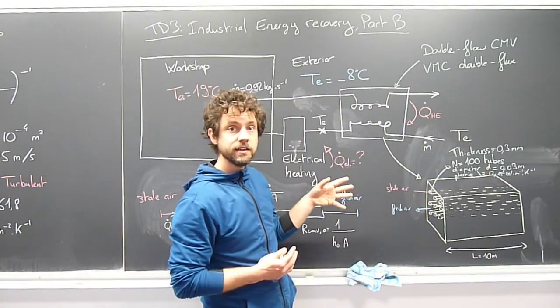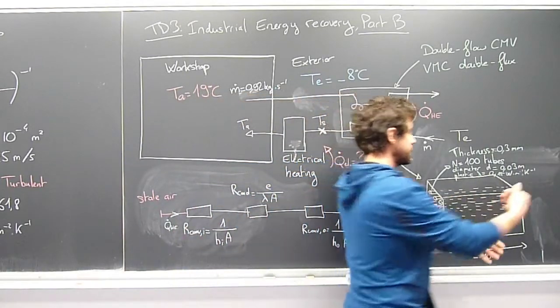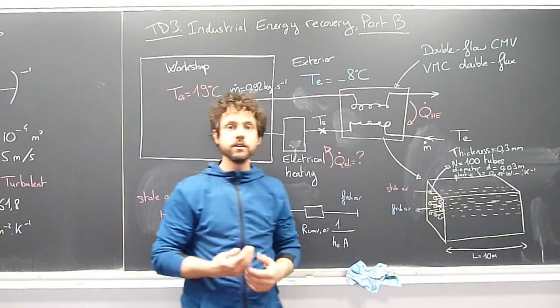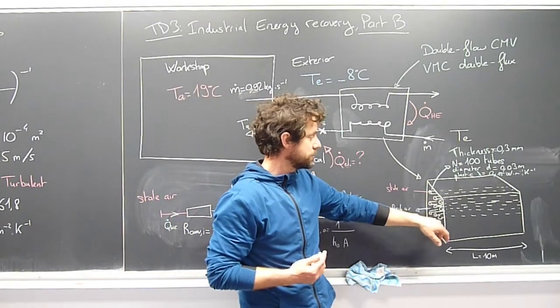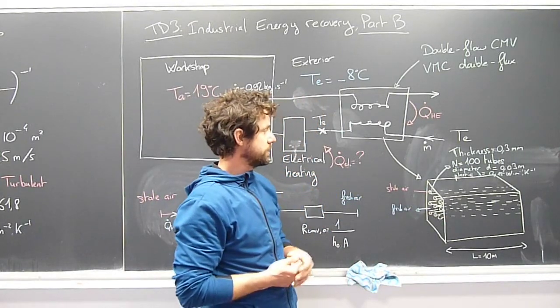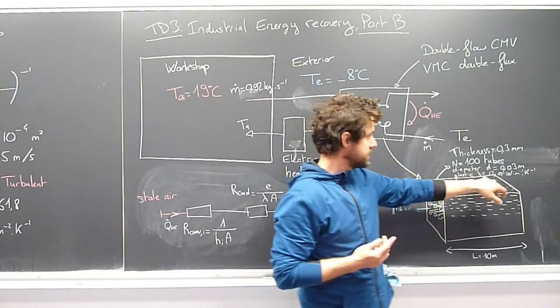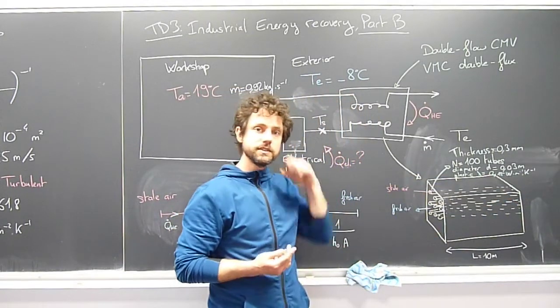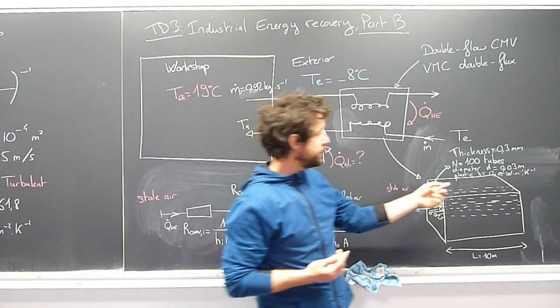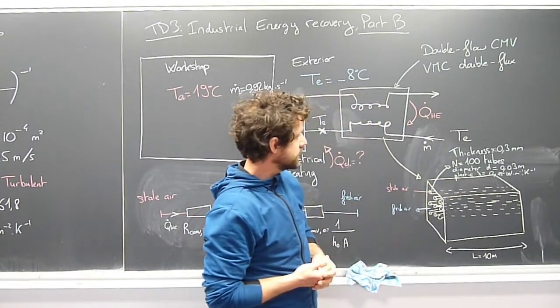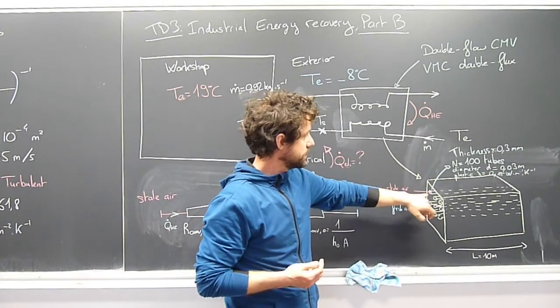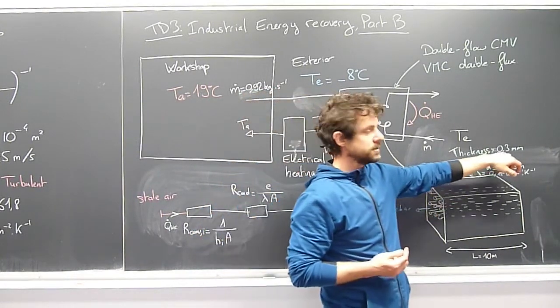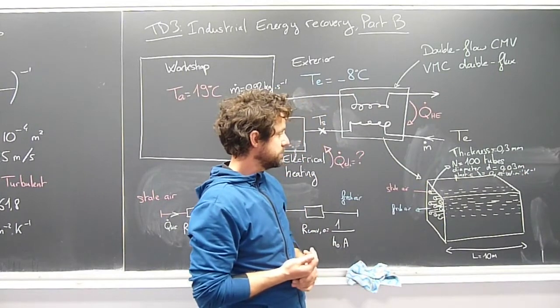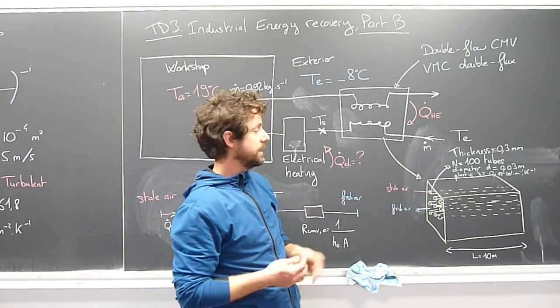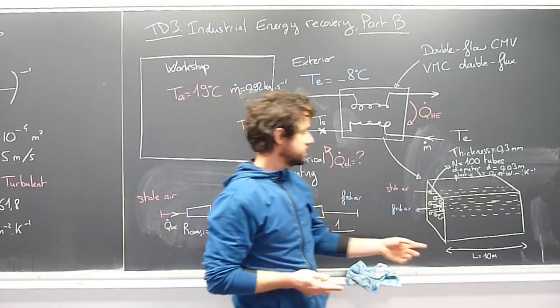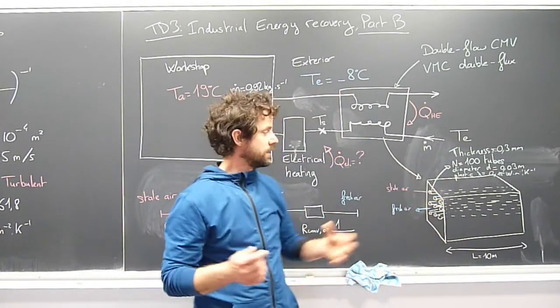The stale air goes through the tubes, and the fresh air comes in counter flow around the tubes. These tubes are made of plastic, which has low conductivity, but they are very thin: the diameter is 3 centimeters and the thickness of the plastic is 0.3 millimeters. The length of this whole heat exchanger is 10 meters, so it's a very long heat exchanger.